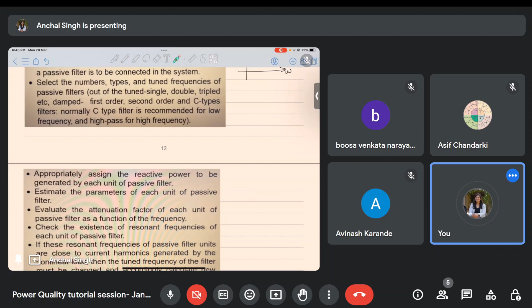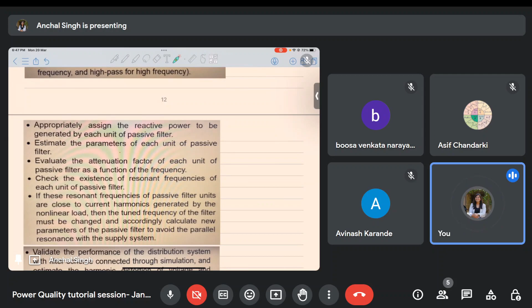And after that, based on the reactive power assignment, we find the estimate of the parameters of each unit. What will be the L value, C value, R value, all these things. Then we evaluate the attenuation factor for each unit of passive filter as a function of frequency. Then we check the existence of resonant frequencies of each unit. So this is the place where the design is complete.